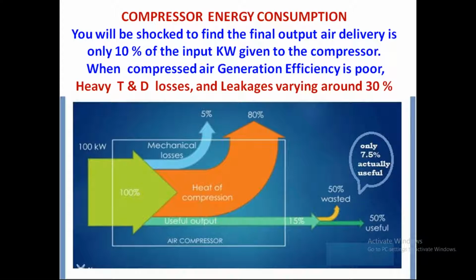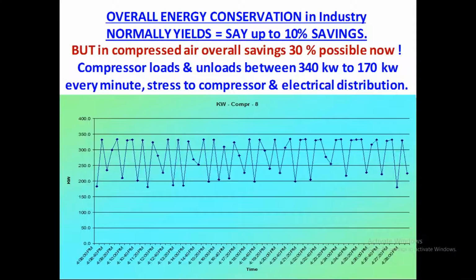The leakage, you cannot generalize. Normally the energy auditors generalize that compressed air leakage will be 30% or 50%. It is not like that. In many industries, they are maintaining less than 10% also. It is a point to note for the energy auditor. Because of leakages in the compressed air header, on the piping, and on the branch piping at the tail end, this compressor is operating from 160 kilowatts to 350 kilowatts. It is a 325 kilowatt machine giving 2000 CFM delivery.